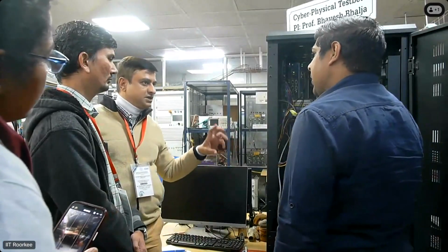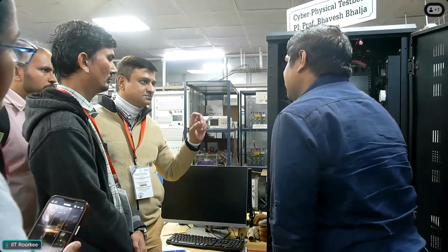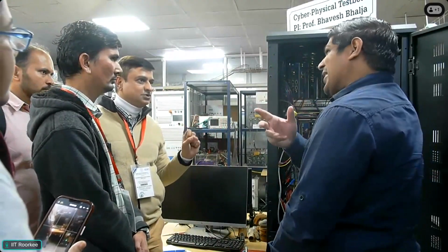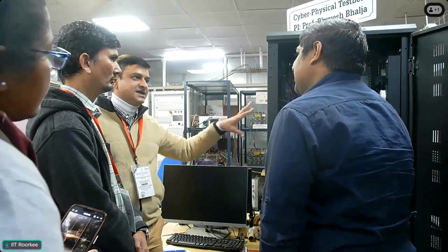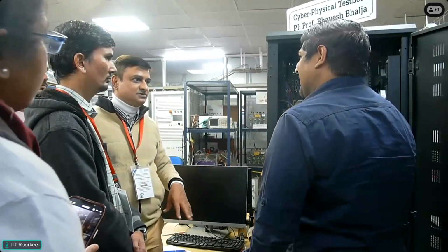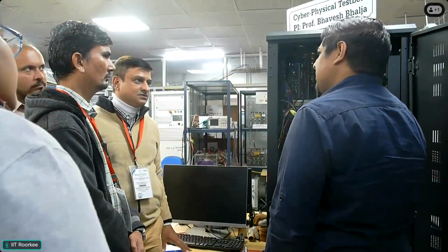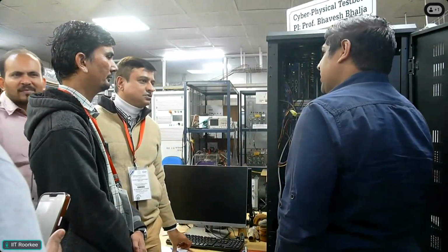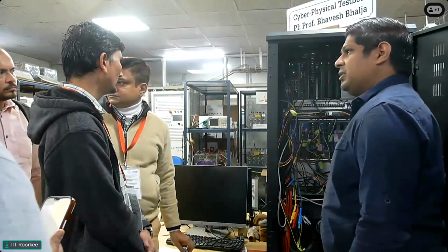Can virtual PMUs of any make be configured? It is not make specific. A virtual PMU is from RSCAD, it doesn't ask for any make. It gives the same feature and works just as a PMU. It is calculating the phasors, getting time stamped by the GPS clock, and sending the phasor values.